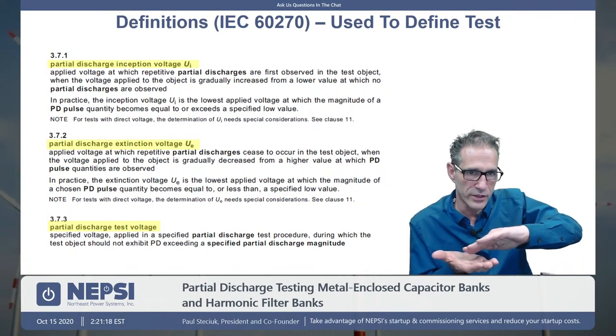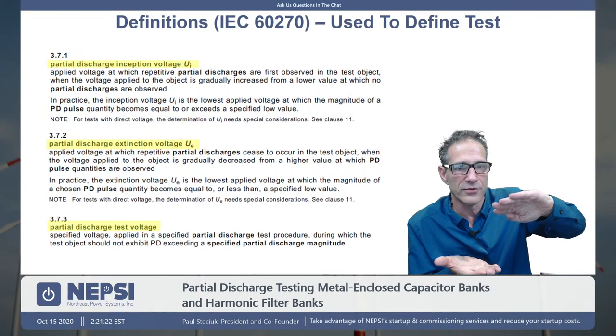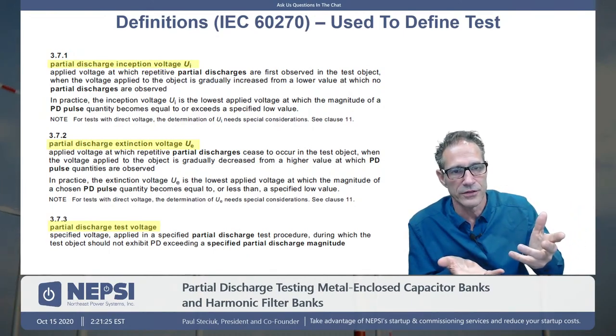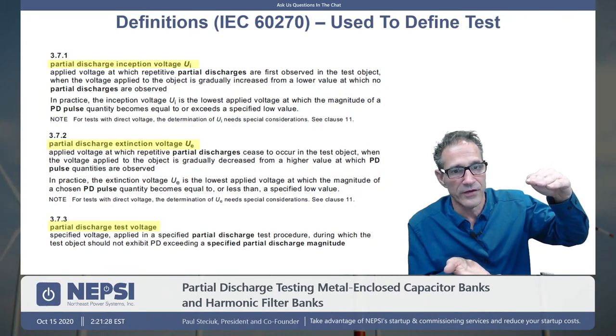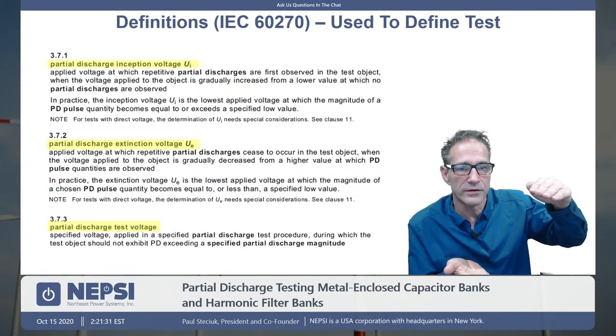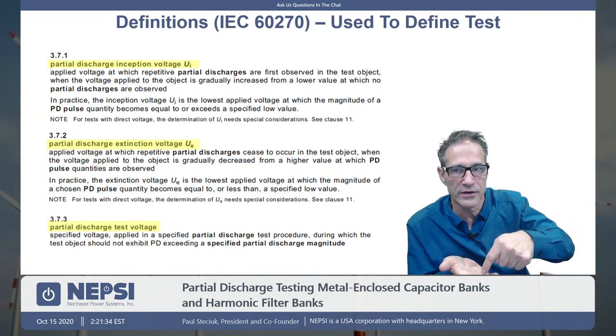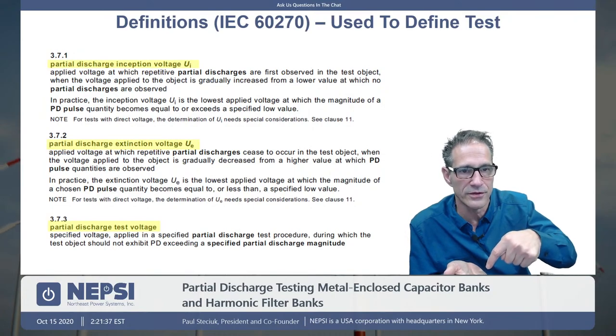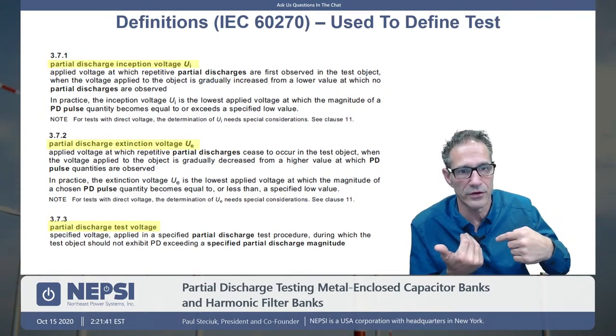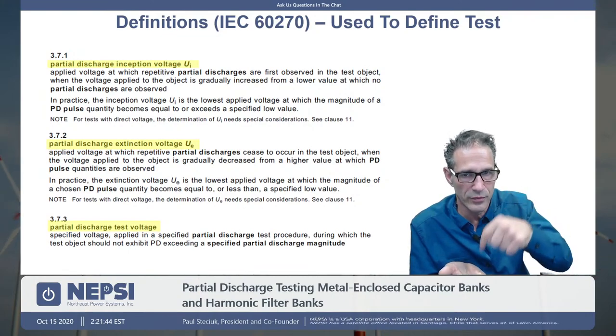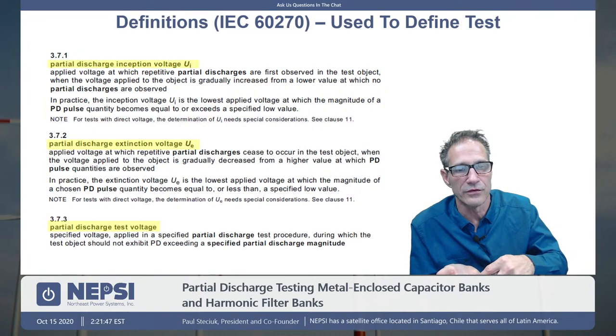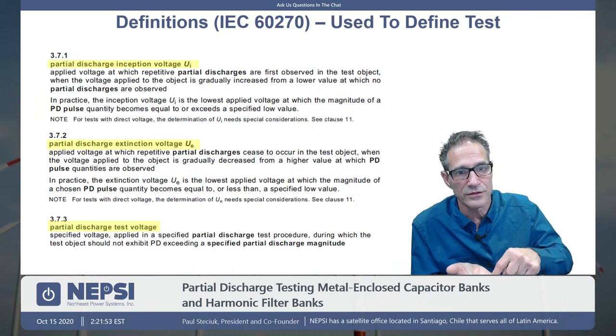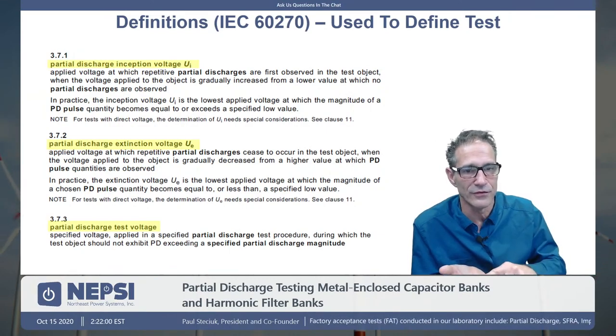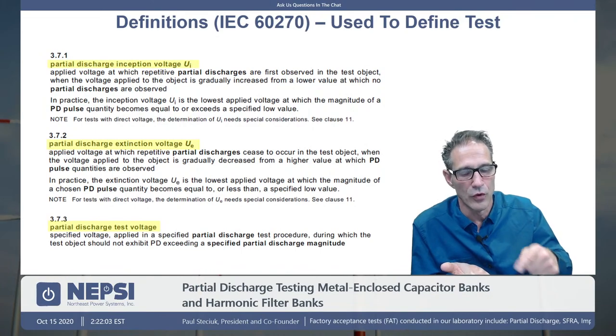So think about this. We bring the system voltage up. As you bring it up in voltage, at some point you're going to start getting partial discharge, and we will continue to raise at that point to some value. And then after a certain amount of time, we will bring the voltage down. When we bring the voltage down, at some point the partial discharge will cease to exist. It will drop down below, and what we're looking for on our side is 100 picocoulombs. And when it gets down below 100 picocoulombs, we would call that the extinction voltage. One of the things about inception and extinction voltage is oftentimes the extinction voltage is below the inception voltage. And really when you're testing, you want to make sure that your extinction voltage is above your normal overvoltage of your system.